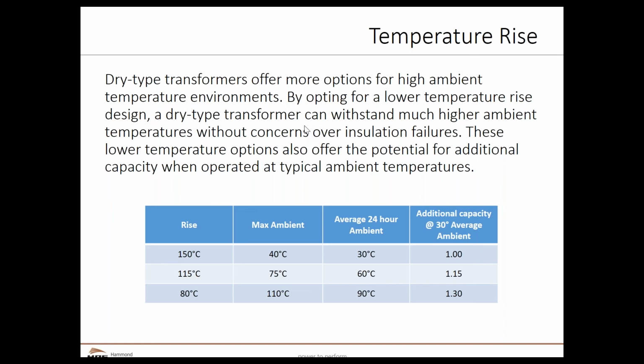So depending on what ambient temperature you're going to run that transformer at, I can either run it at higher ambient temperatures or I can get some additional capacity. When we look at the additional capacity, you can see that that's at a 30°C average ambient versus the column just to the left of that, which has higher average ambience. So again, a lot of additional temperature rise options with dry type that can affect the design protocols and the equivalent kVA that you would be specifying and using.